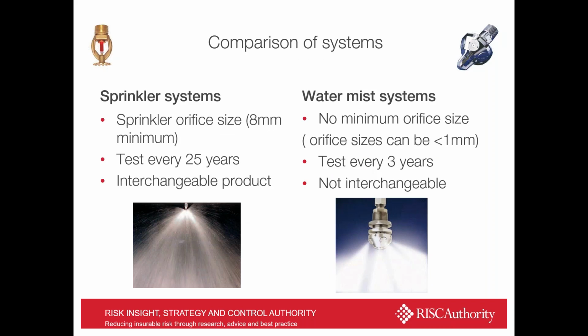There's also looking at orifice sizes themselves. We mentioned the minimum orifice size for sprinkler systems, around 8 millimeters, and as such, they get tested every 25 years, and the products are interchangeable. If your heads need replacing, you can go to any number of manufacturers and put their head in place of it. Water mist nozzles have very much smaller orifice sizes, and we know in our laboratory, even with trying to be fastidiously clean with our water, we do get issues occasionally, and as such, these need testing every 3 years, and they're not interchangeable between systems. You do need to go back to the original OEM provider for nozzles if more are required.